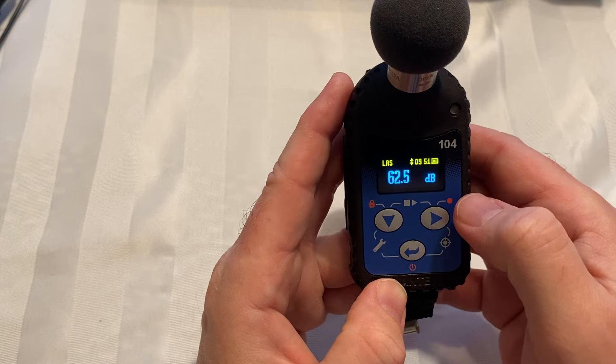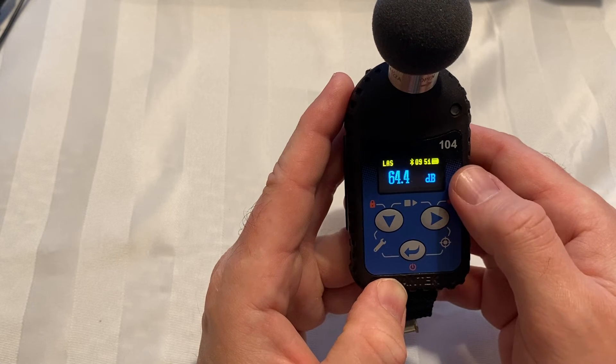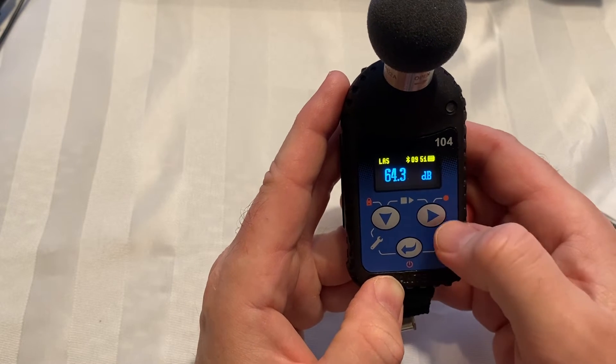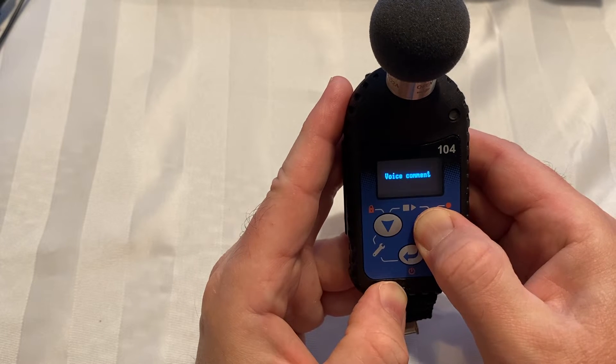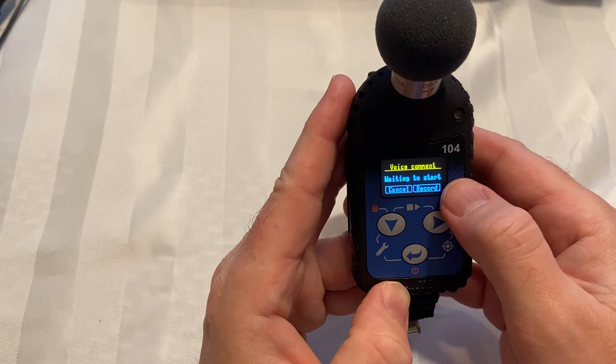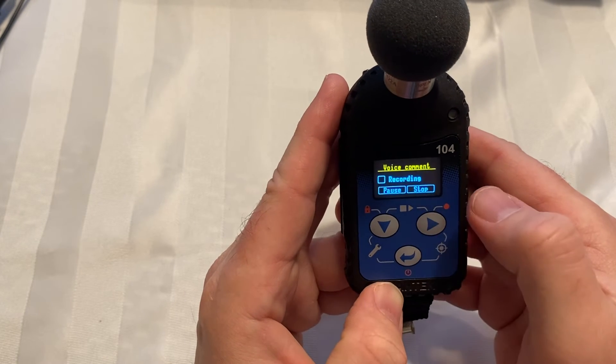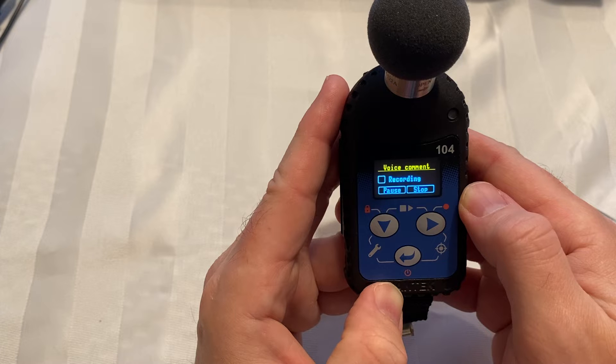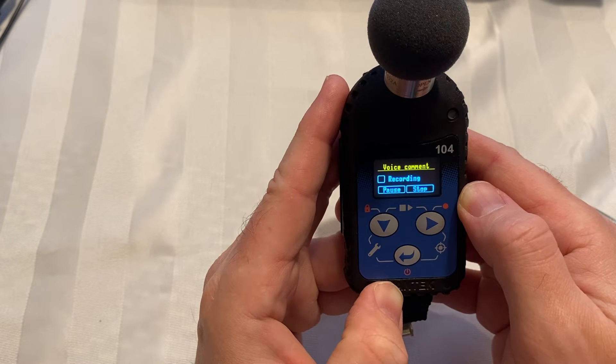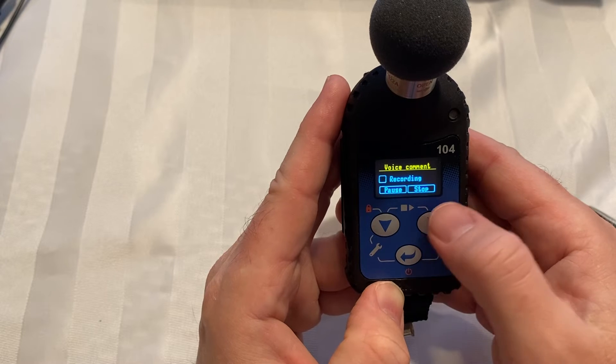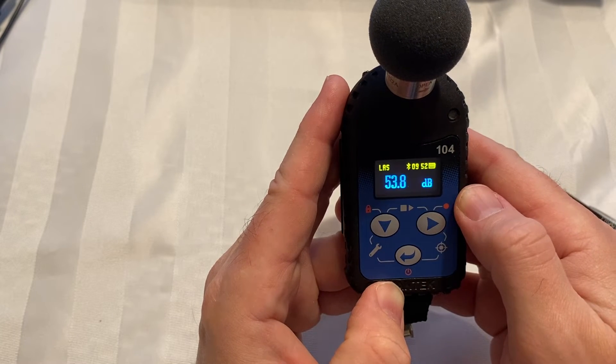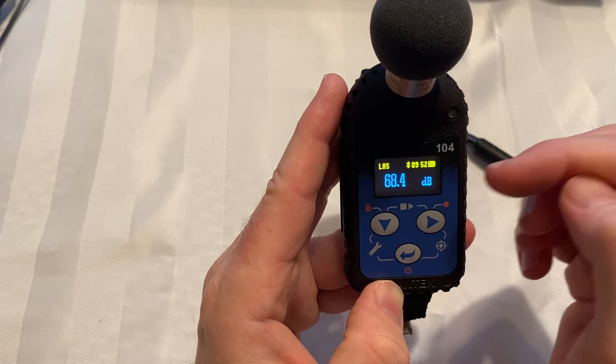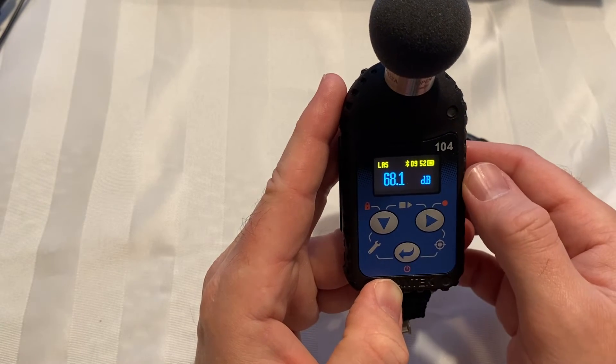So let's push the button to turn on the display again. If I hold down this key for three seconds, it's going to give me an option for a voice comment. Now I can start the record or cancel that. 'This recording is happening in the production area, January 6th.' Okay, so that voice comment would be stored with the data that I'm going to collect today.